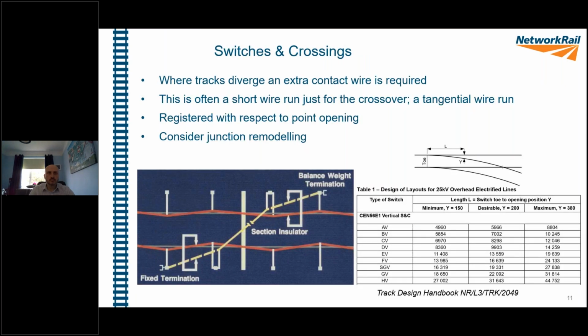Another area which is quite critical really is switches and crossings and how we electrify them. Usually for a crossover, as the bottom left photo here demonstrates, we have an extra wire run, demonstrated here as yellow. This extra wire run is quite short and is usually used just to wire the crossover itself. At one end we have a fixed termination, where the contact and catenary wires are fixed via an insulator directly to the structure. And at the other end we will have a balance weight or a tensioning device to maintain the tension for the crossover.